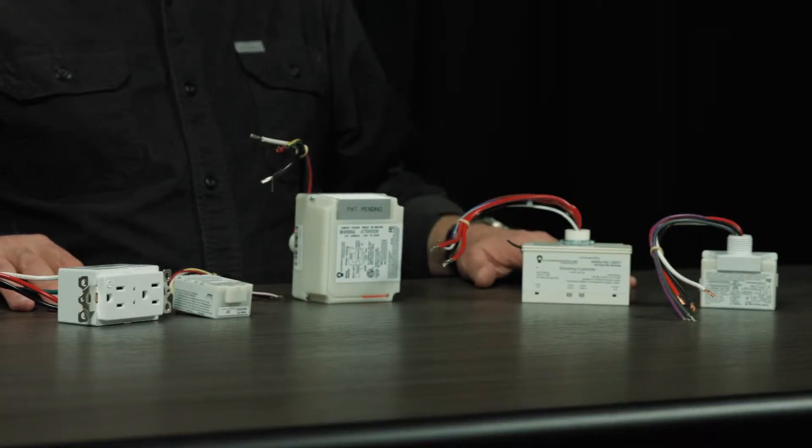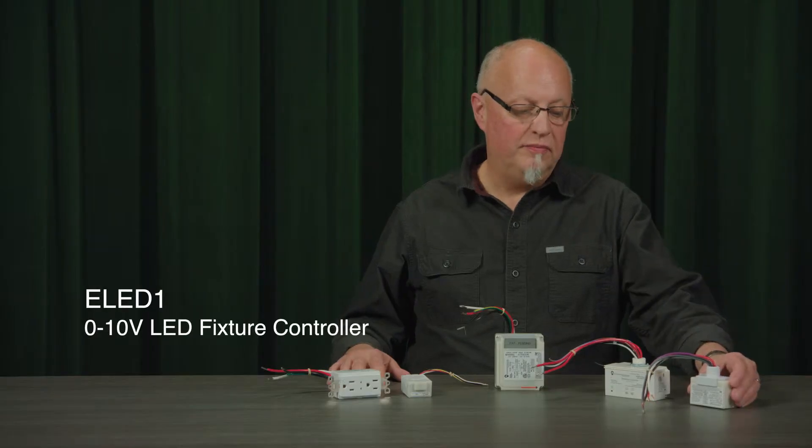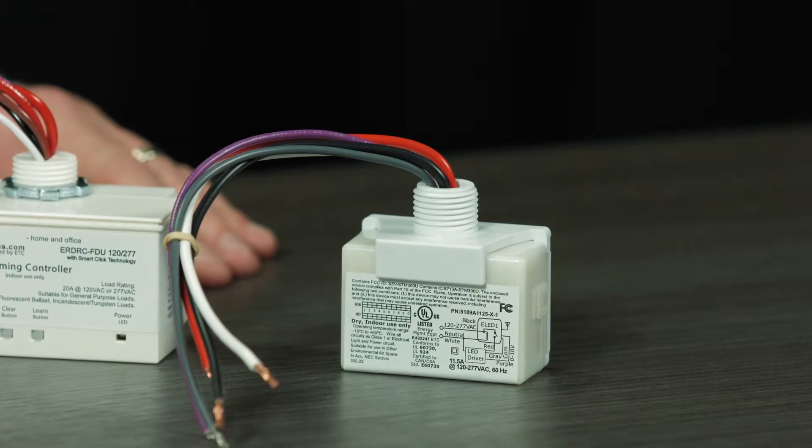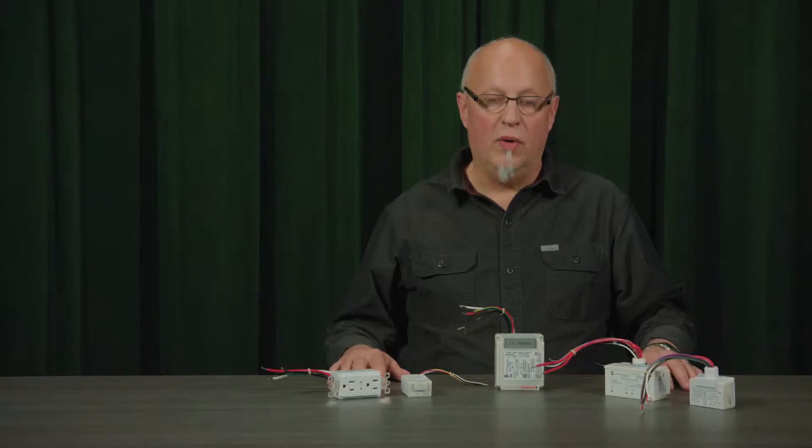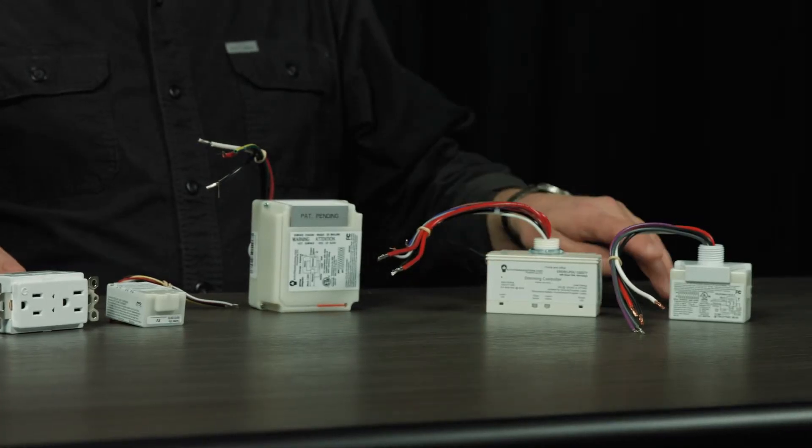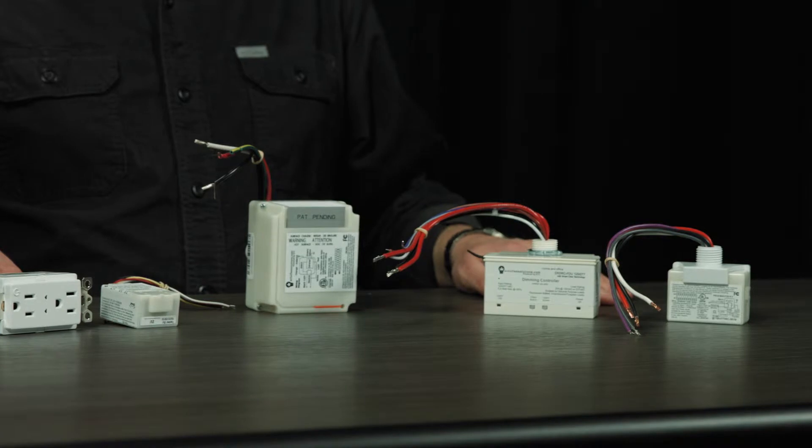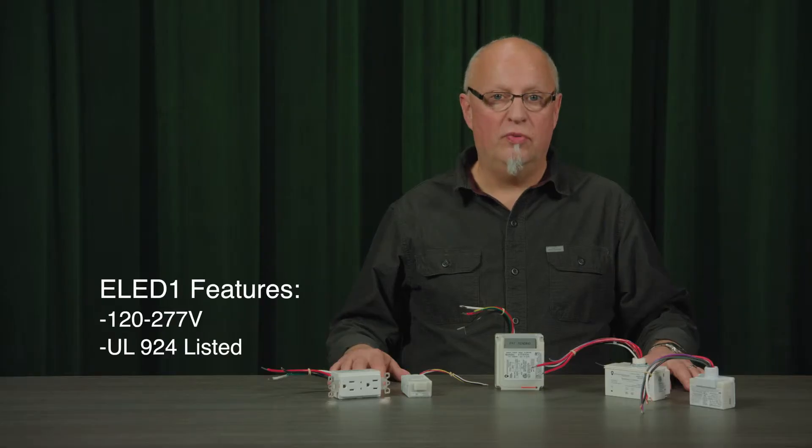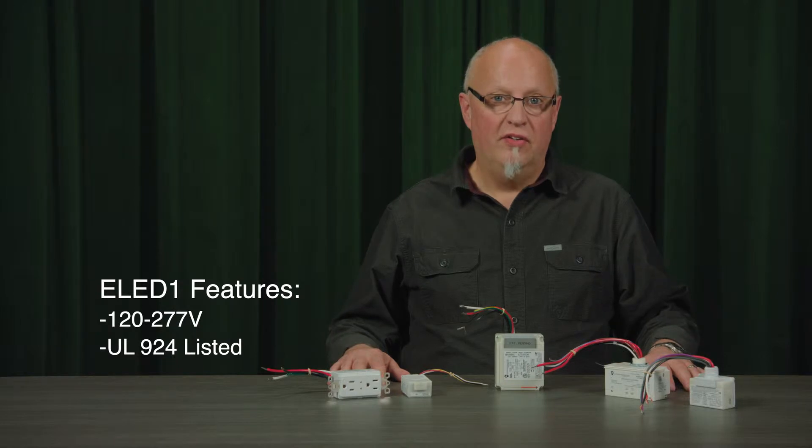Starting on my left is our newest product, the E-LED1. It is a 0 to 10 volt controller. Its power supply is versatile, going from 120 all the way through to 277 volts. It is a power pack style that I've got here, but it comes also in a strap mount model for use inside fixtures. It is a UL924 listed device and is applicable for emergency lighting fixtures as well.